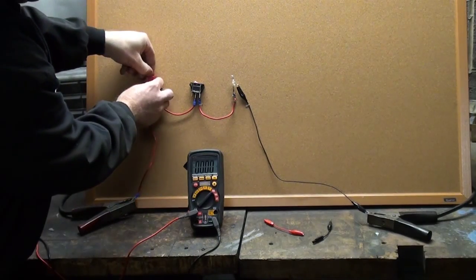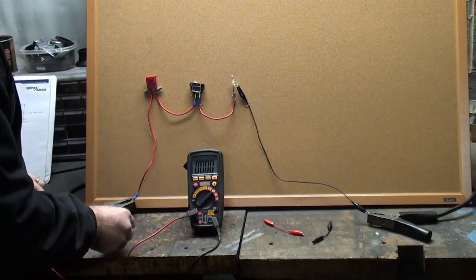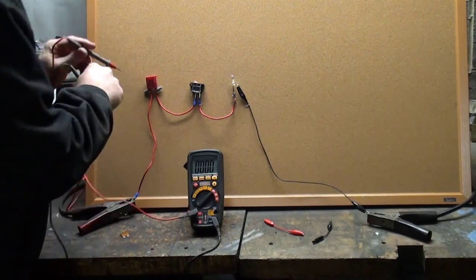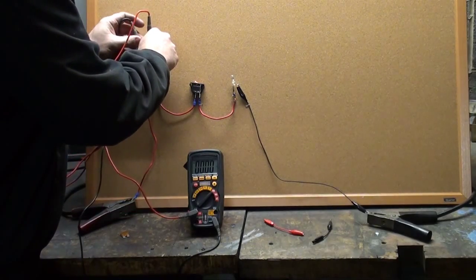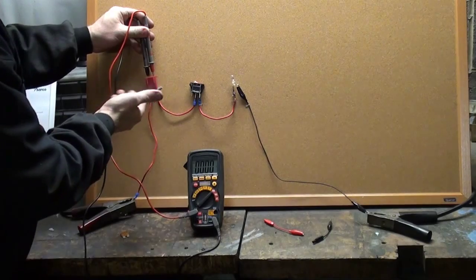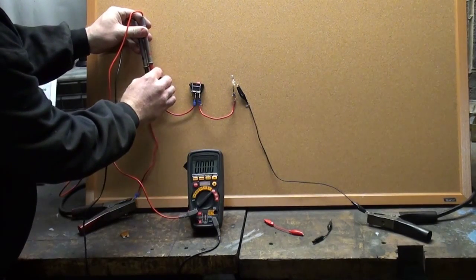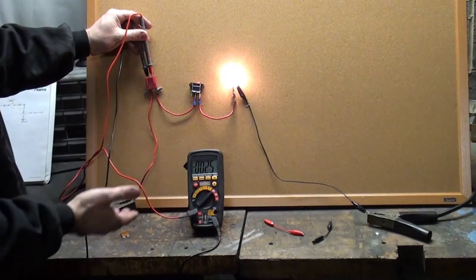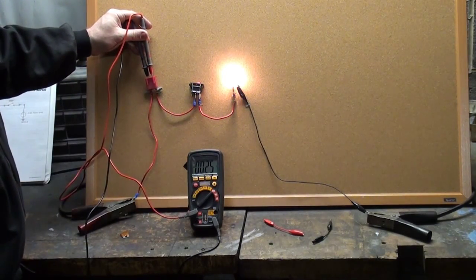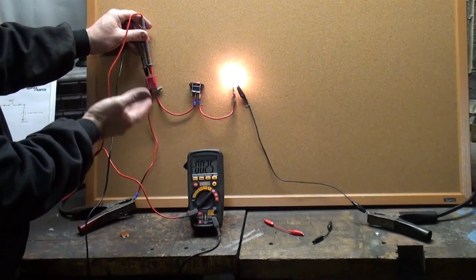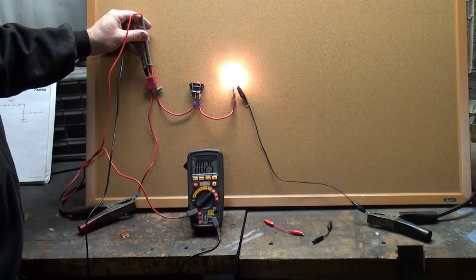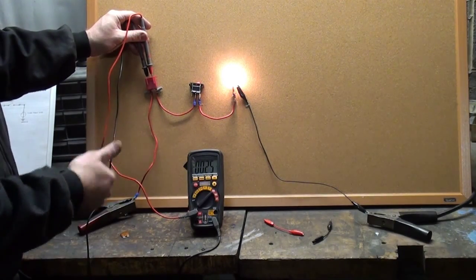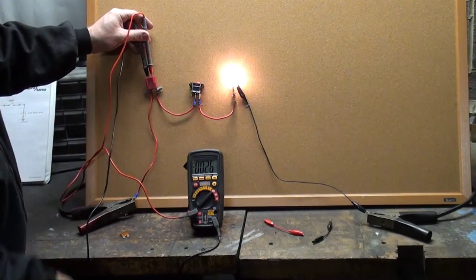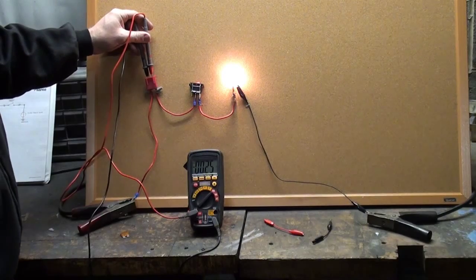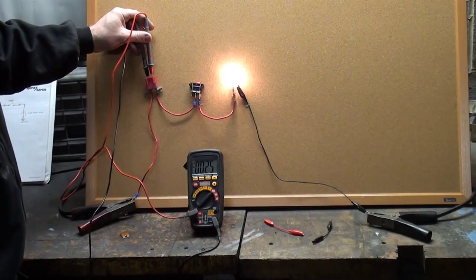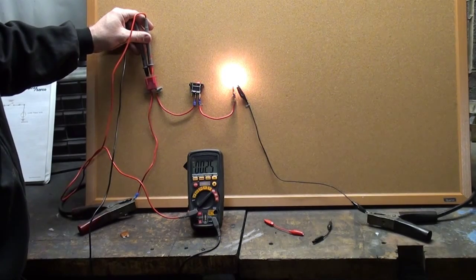We could simply pull the fuse out, then insert our probes into the fuse holder. We've pretty much opened the circuit in another spot. So if I power up the circuit, I have a good connection, and as you can see, I'm checking the amps through this open in the circuit. I just created a different open in the circuit and got the same amp reading without disconnecting it from its source. I simply removed the fuse, and you could do this in your car as well to check the amps of the circuit by using that open.